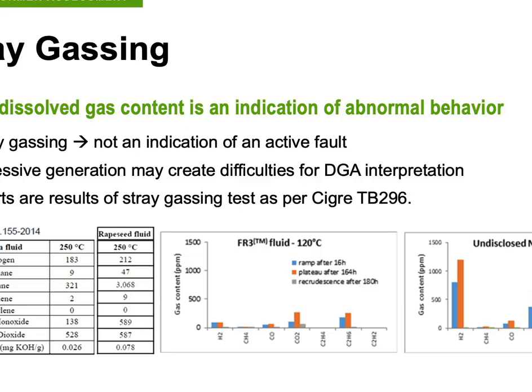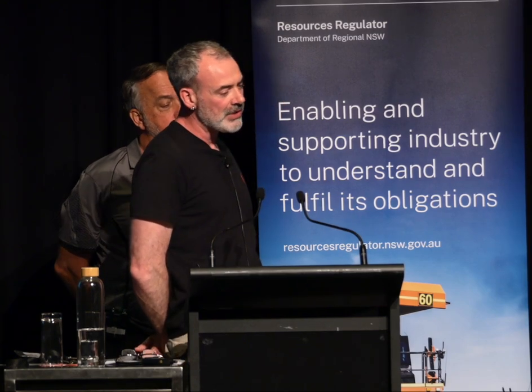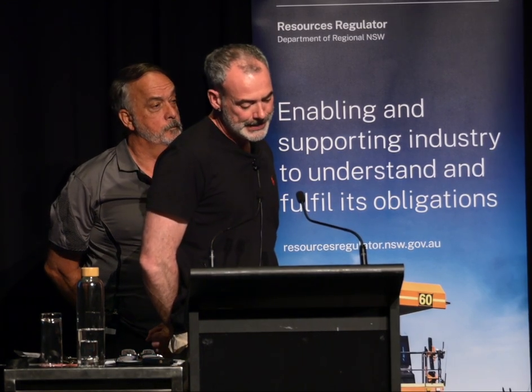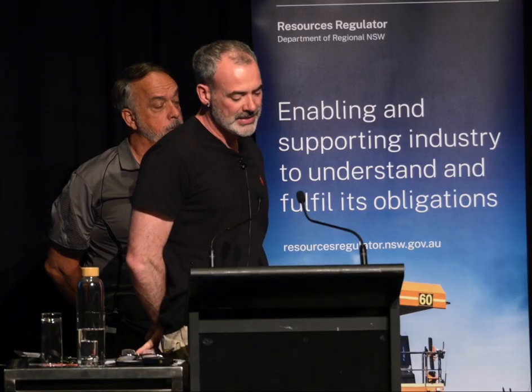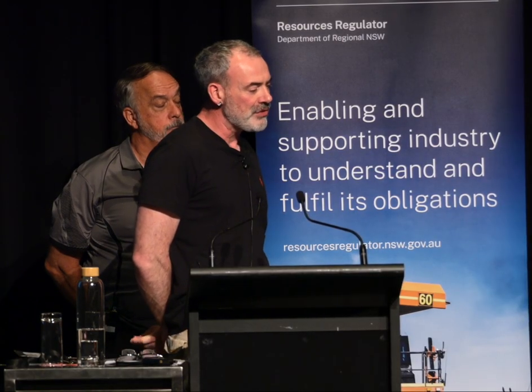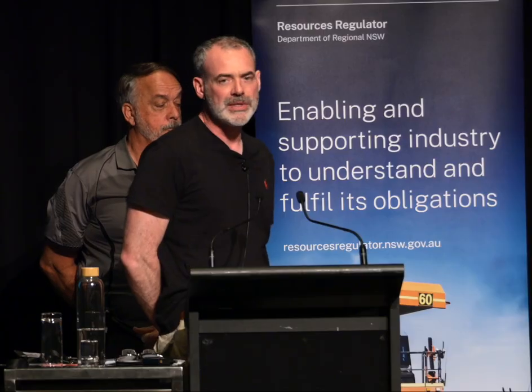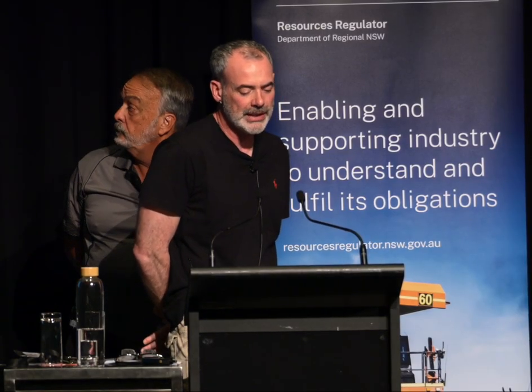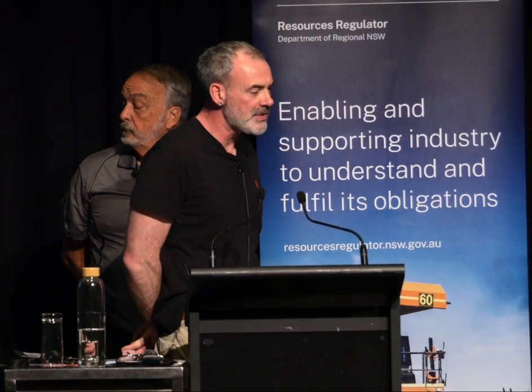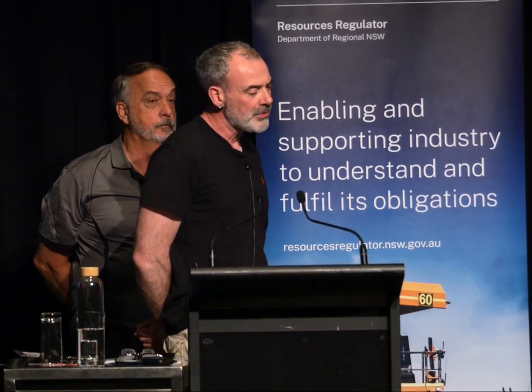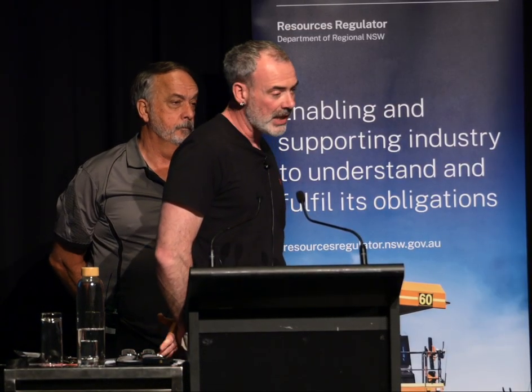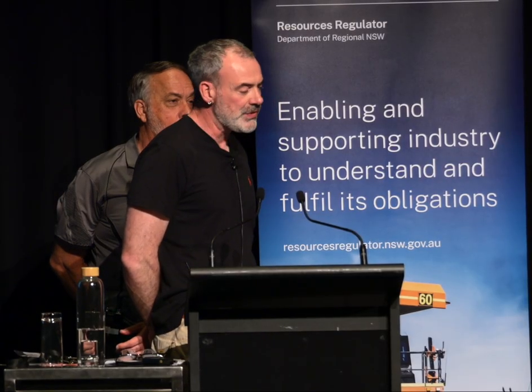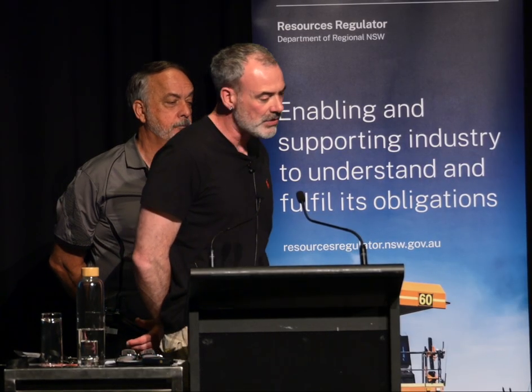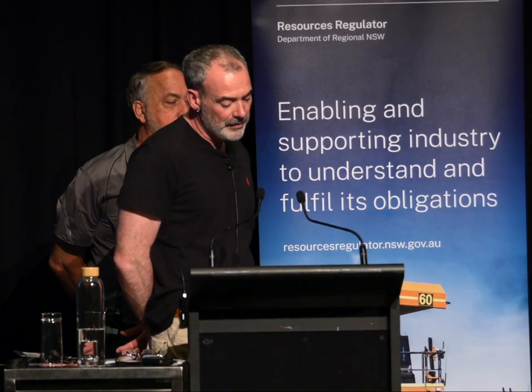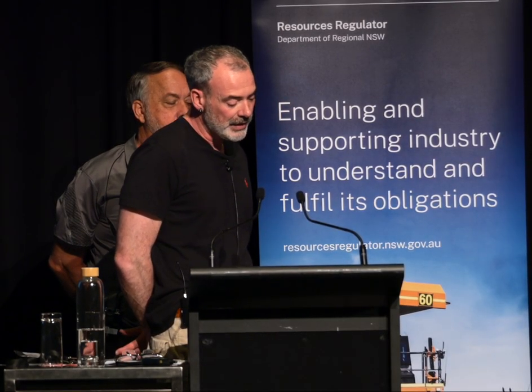Final page. Stray gassing is the occurrence of a situation in transformers filled with ester fluids, which we identify with dissolved gas analysis. So it's gas generation from the fluid. It might be because of a fault, or it could just be heating of the fluid leading to gas generation. But it can be confusing when we do the condition assessment. And from 25 years of operational data with our natural ester, we know that it produces ethane, C2H6, and this is documented in the IEEE standard C57.155.